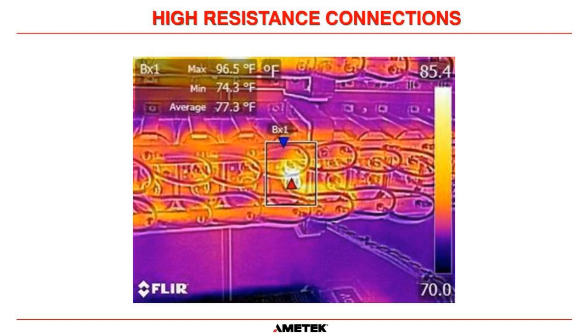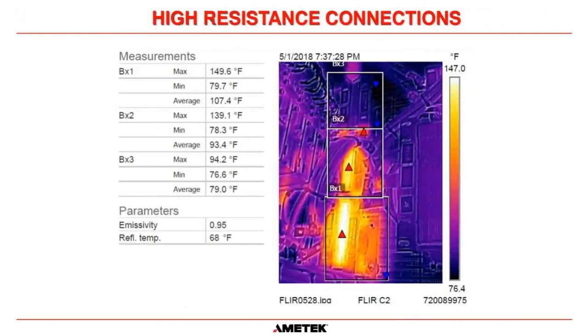And then the opposite of a high resistance connection, in this picture here, it's difficult to see to start off with, but this was actually on a UPS that had just been commissioned. It was a 250 kVA UPS. And on our big UPSs, we have multiple cabinets that need to be bolted together, and the connections between the cabinets need to be bolted together. And that's usually done by the contracting electricians for the plant.